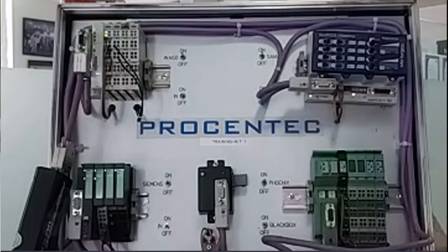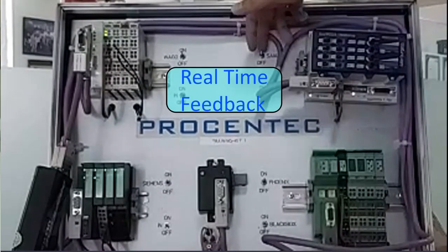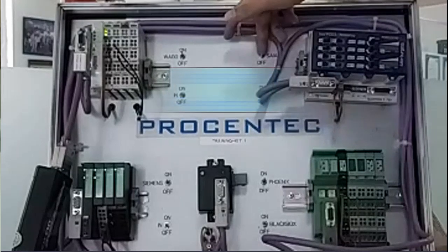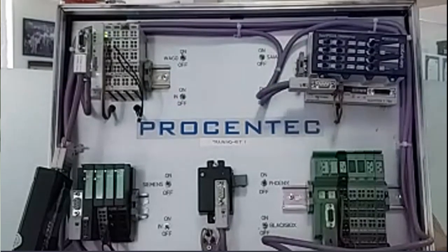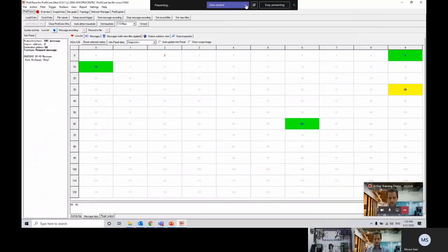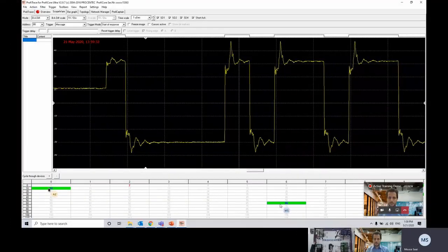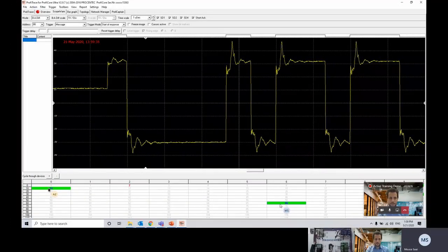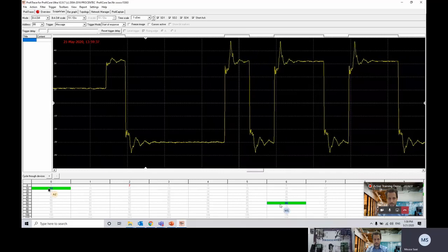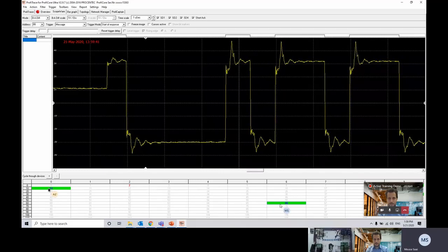So I'm going to take out the Saia and switch it out of the network. Then you take a look back at the screen. Okay, you have control already, and you see that the Saia at the address 39 is lost. Yeah. So now I'll put back the termination in the network, and you can see what will happen directly. I'll just do it while you see it.